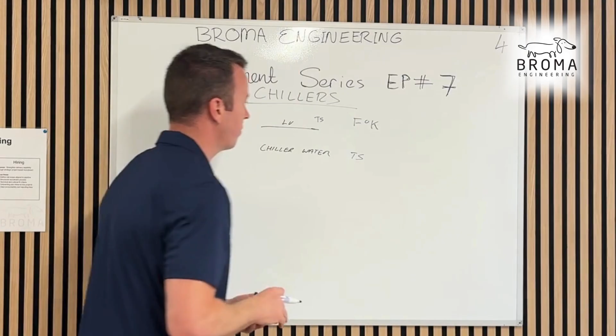LV cable needs a technical submittal, needs to be approved. The lugs, landing should be planned. Colors, right size, manufacturer's approved, so a technical submittal goes in for that. You could have a first of kind needed, FOK, first of kind for pipework for the first chiller that's set in place. So make sure your first of kind list is there. Sometimes the quality manager does that, but I think the commissioning manager should cover everything to do with equipment, and everything to do with CSA should be quality. That's the way I look at it these days.